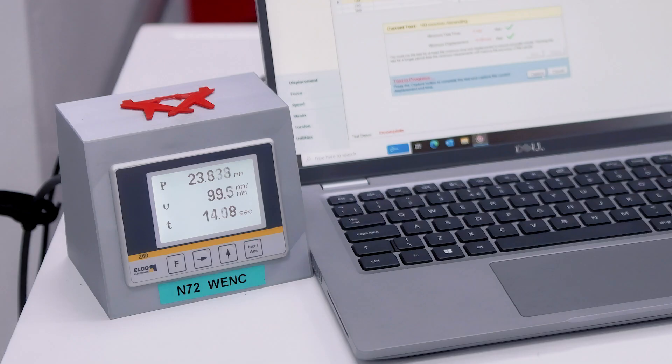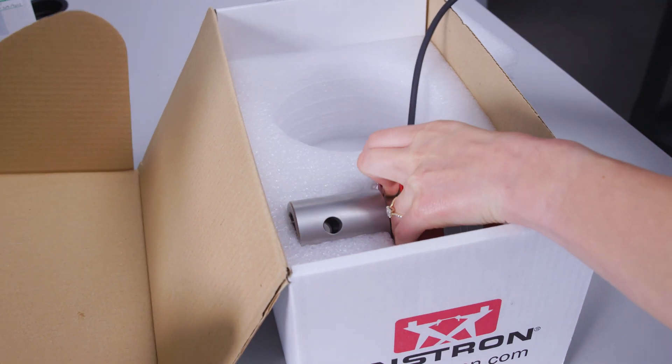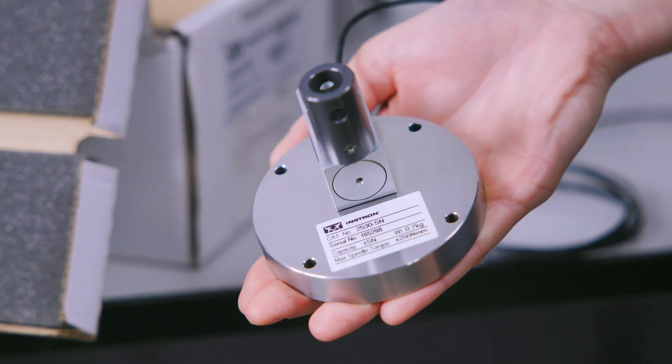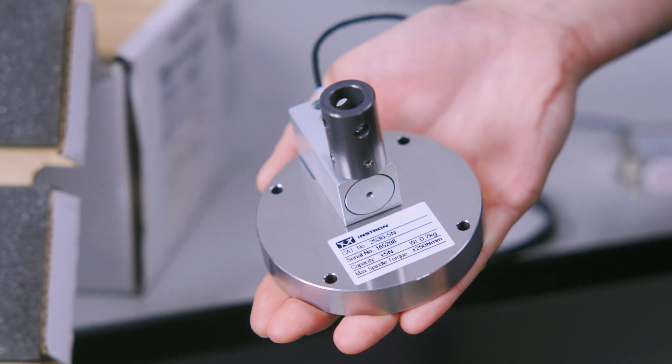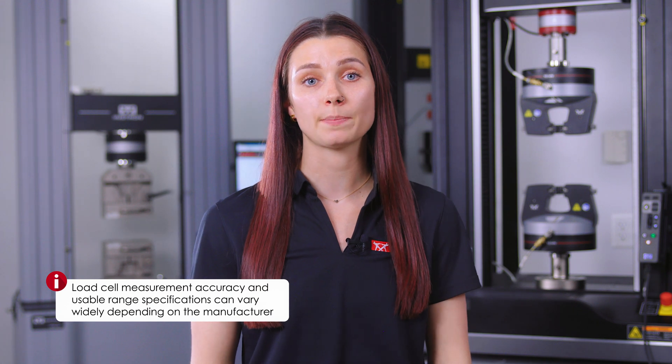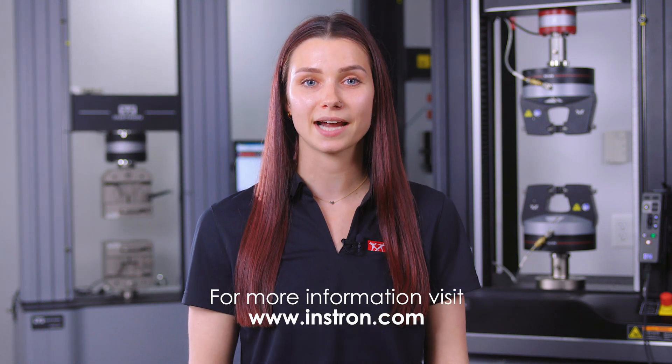Each load cell will need to be calibrated, maintained, and stored safely to prevent damage. Smaller load cells are more susceptible to damage, and calibrations are critical to ensure you are getting the data you need. It's important to keep in mind that load cell measurement accuracy and usable range specifications can vary widely depending on the manufacturer, so I would recommend discussing this topic with your equipment supplier. For more information, visit our website or contact us with any questions.